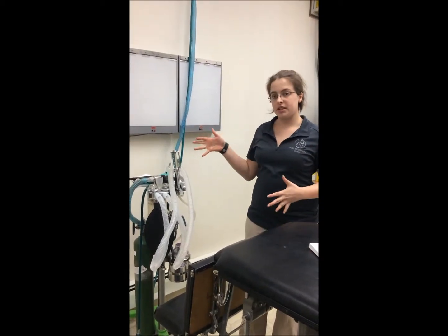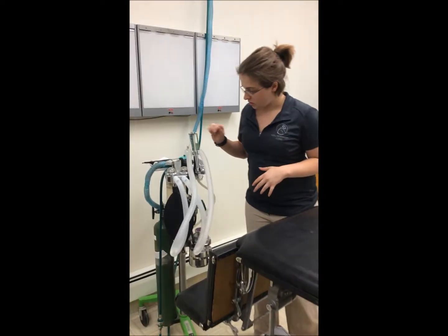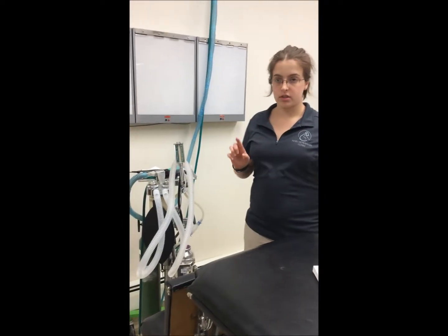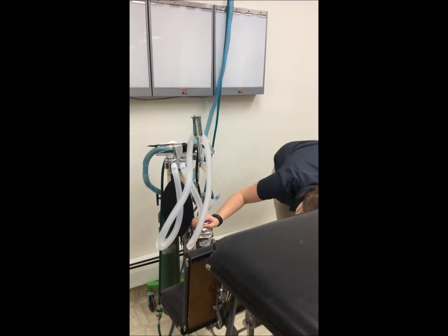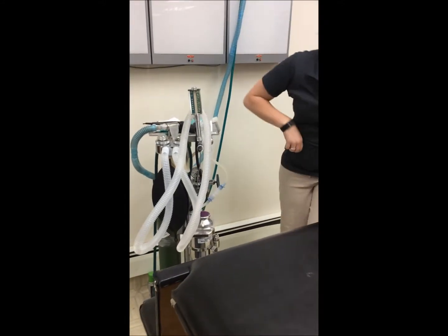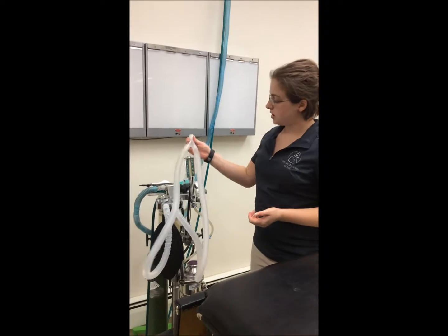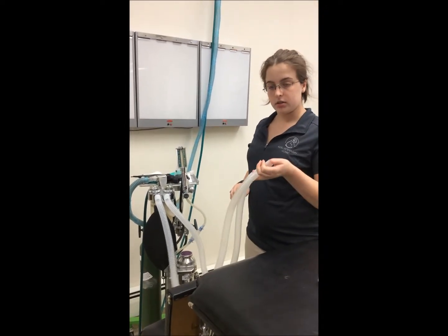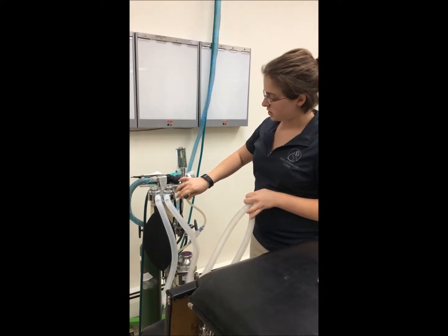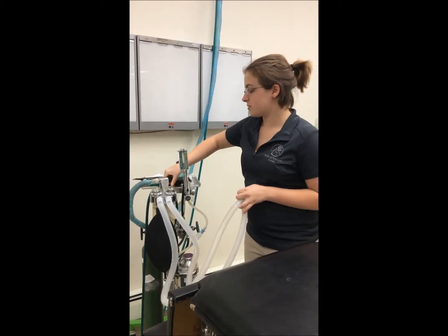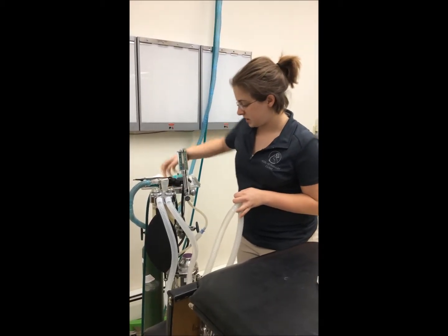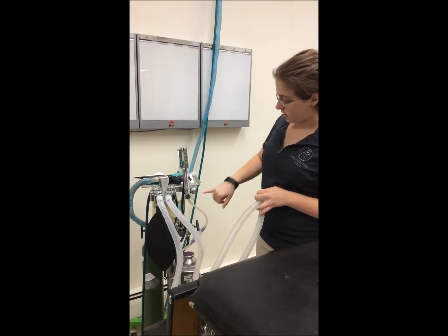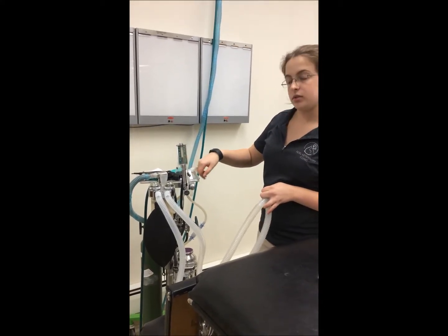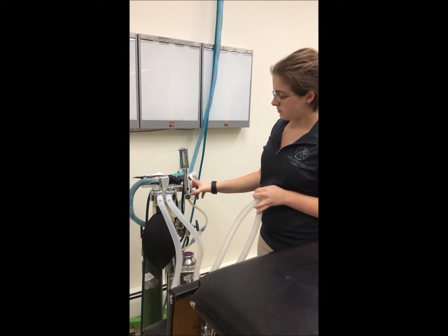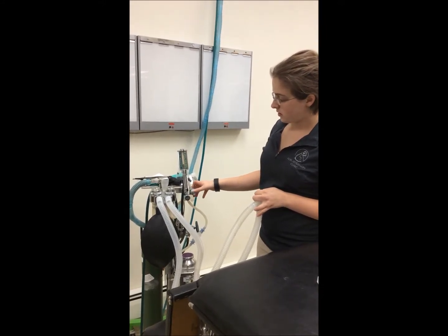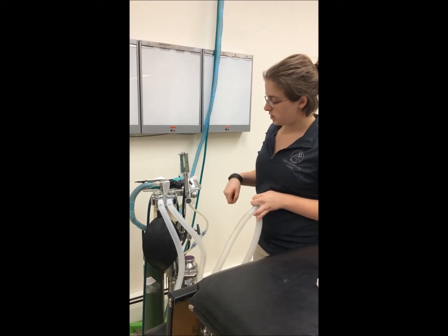Now I'm going to perform a leak test on this anesthetic machine. My main oxygen source is on, and there's a decent amount of liquid in the vaporizer—it's just been filled. I'll close off the tube, turn on the oxygen, and close the pop-off valve completely. Then I'll hit the flush valve and make sure the bag level doesn't drop. It went right back to where it was supposed to.